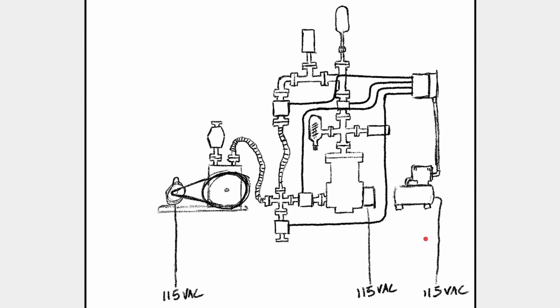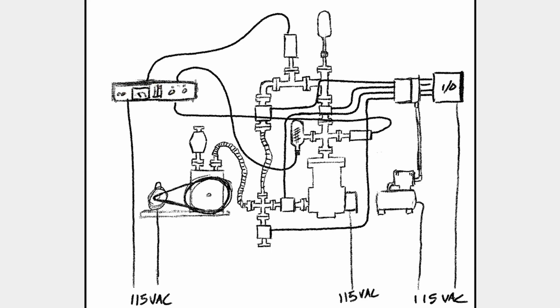Here you can see that our air compressor is going to mains, as well as the controller for our turbo, and of course our mechanical roughing pump. But this isn't all of the electrical. Remember, we have vacuum gauges to consider. And the vacuum gauges are going to have their own controller, which needs to go to mains as well. In addition to the vacuum gauge controller, I've also drawn the pneumatic system controller, even though I'm not exactly sure what this is going to be yet. But I have a feeling it's basically going to be an Arduino with some MOSFETs. And there you have it, the complete system. Looks pretty good to me.